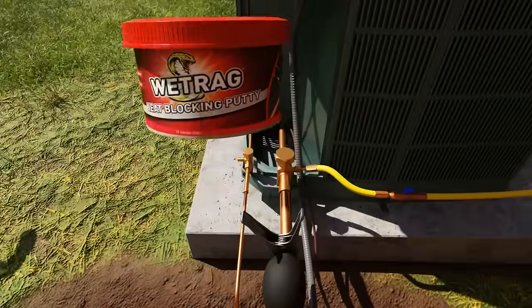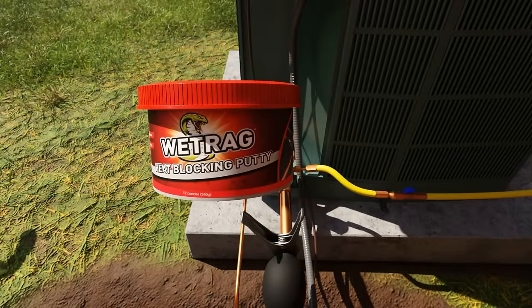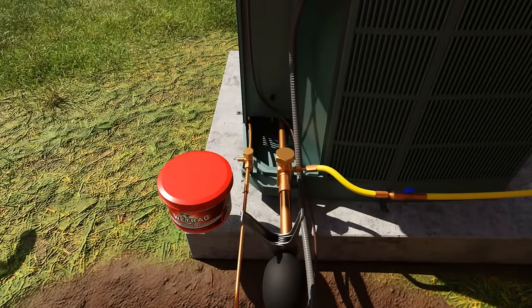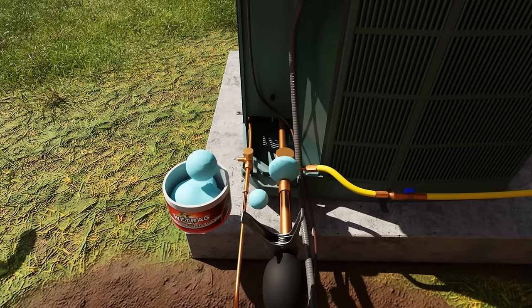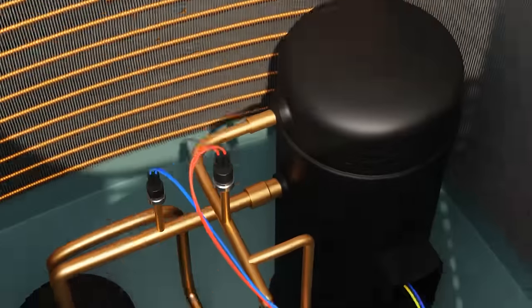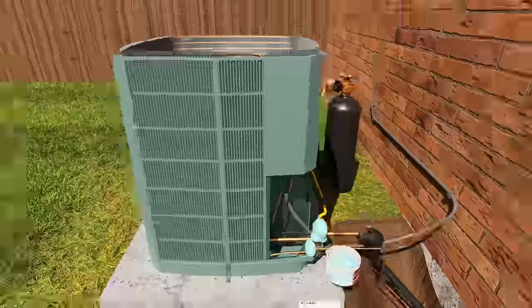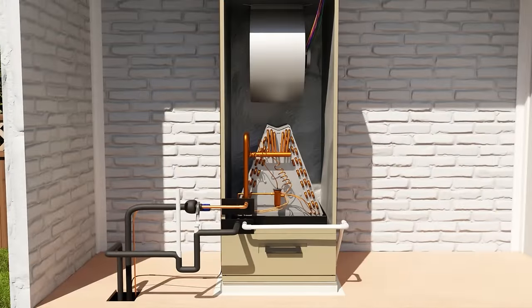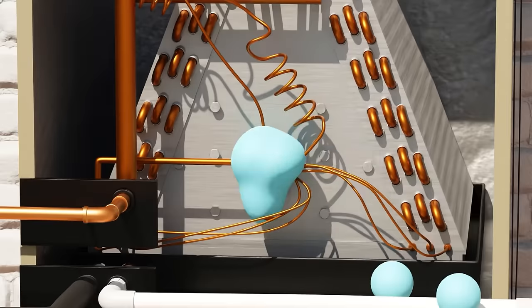To protect the critical system components while brazing, we're showing using wet rag heat blocking putty from Refrigeration Technologies. We use this to protect things like service valves, the paint on the compressor, expansion valves, and sensing bulbs.